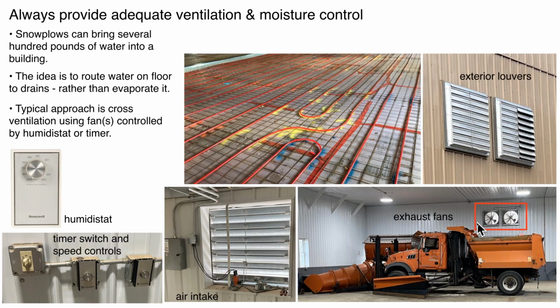But you can also put a humidistat into a building like this and set it so when the humidity rises to a certain point, the humidistat, which is just a contact closure, would activate those fans and bring enough fresh air in from the outside to keep that moisture, that humidity, under control.